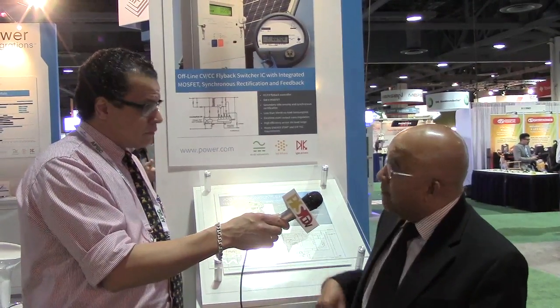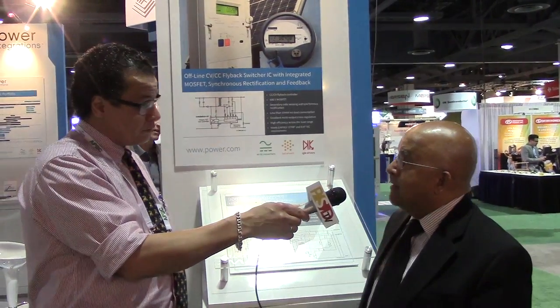That's actually a very comprehensive facility you have there in Germany. Yes, in fact, as far as I know, we are the only independent company that has the facility to run an inverter continuously. We have what's called a ring inverter, because you have to do something with the power you generate, so we feed it back. Even then, the losses alone are so high we need liquid cooling, and all of the heat has to be removed from the building. So it's a pretty significant installation, and our customers come to our facility and use it.